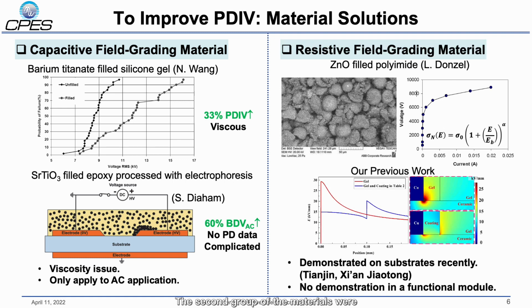The second group of the materials were called resistive field grading materials. Zinc oxide and silicon carbide were usually used to fill into the polymer matrix. As shown in this curve, they are more insulative under low electric field but more conductive under high electric field. We proposed to use this kind of material as a coating or shielding layer at the critical regions in the power module prior to the primary insulation, for example, silicon gel. We used the FEA simulation tool to model this kind of material and find the desired IV curve of the material for the medium voltage power module applications.